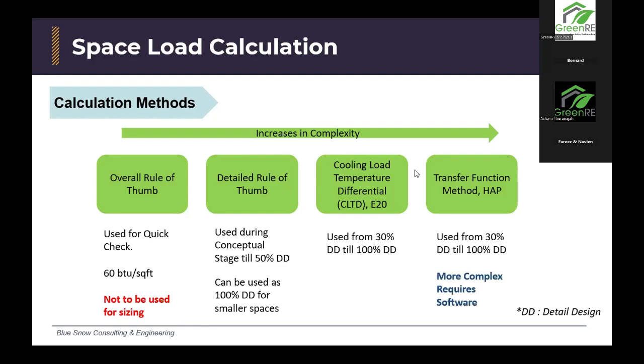So what is meant by a load profile? A load profile is how your building's heat load is going to play out by the hour throughout the day. So the CLTD will tell you that. In fact, it will even tell you how it will be based on each month. But it is not as complex as the final method, which is the transfer function method, which is often done using software, because if you're going to do it in an Excel file, it is going to take you a long while, but that will tell you with precise detail how your load is being used throughout the year.